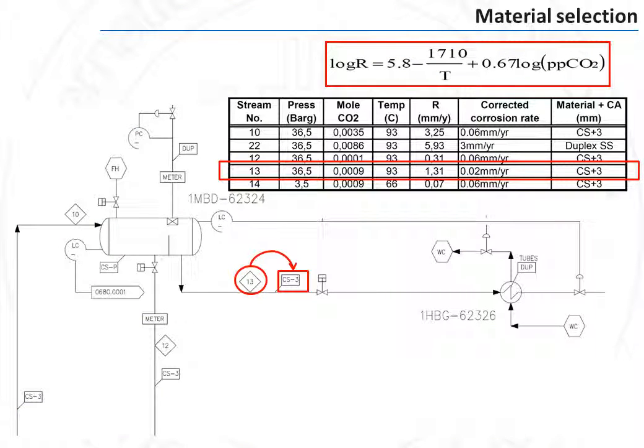The required input data for this calculation are shown on the heat and mass balance. Indeed, the heat and mass balance indicates for each stream the temperature, the pressure, as well as the composition. Therefore, the calculation of the corrosion rate can be done. This corrosion rate is then calculated over the entire facility's design life, such as 20 or 30 years, by simply multiplying the yearly corrosion rate by 20 or 30.